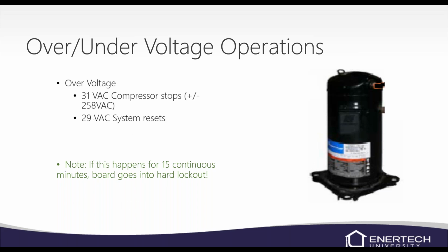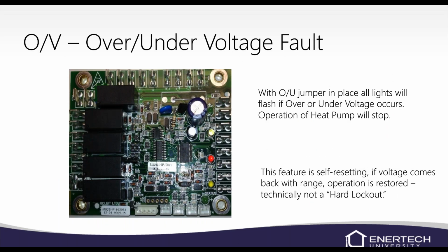The 29 volts, it will self-reset. The under voltage is 18 volts, which is roughly 190 volts coming in on the primary side. And then 20 volts will reset the board itself. There is an under-over voltage jumper or dip switch, depending on what board you have. If we were to remove that jumper or flip that dip switch to off, it's labeled O/V. It should be OU, but the Europeans like to use V for U. So OV is what it's going to look like on the board, and that stands for over or under voltage.